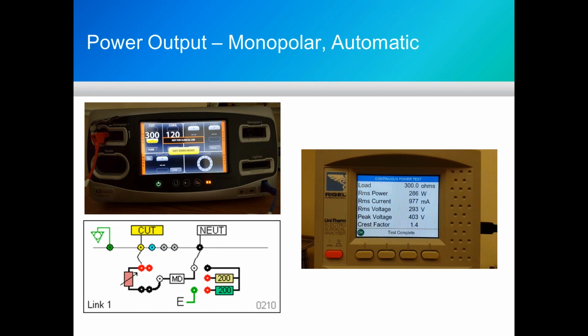In a cut waveform, the amplitude of that waveform is constant across the entire profile, across the entire process. So that ratio is pretty consistent. When we go to coag, it's more of a sinusoidal amplitude riding on the waveform. So you're going to see when we do coag tests that the crest factor is going to increase. The blend waveform is the combination of the two.